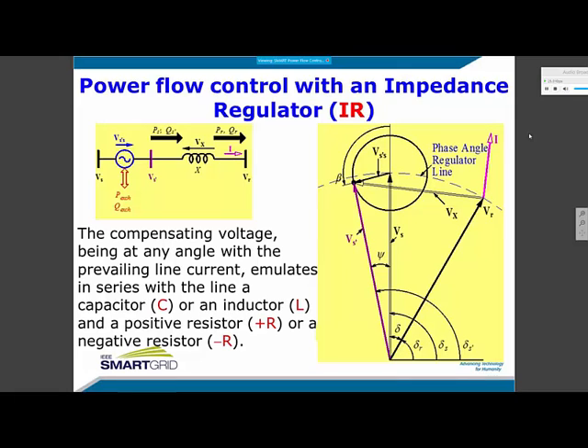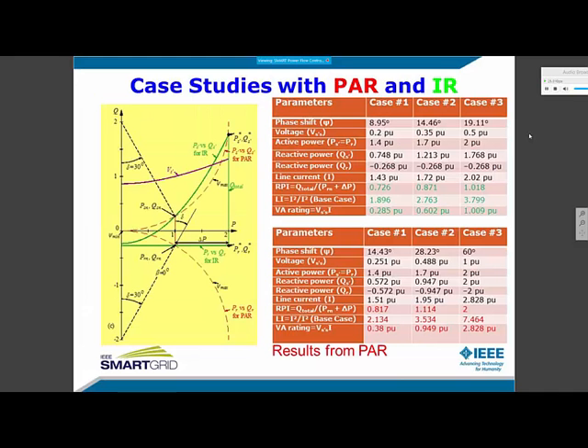The modified voltage is confined within this circle. In comparison, the modified voltage of the line, if we use the phase angle regulator, is along this blue line. Now, this difference of the two characteristics is significant. In a power system, as the flow of power increases, the demand for Q also increases at both ends of the line. The cost of increasing Q demand may outweigh the benefit of increased P flow through the line. As a result, the power flow up to the line's thermal limit may not be attainable. This is a real problem that needed to be solved. An impedance regulator solves this problem.